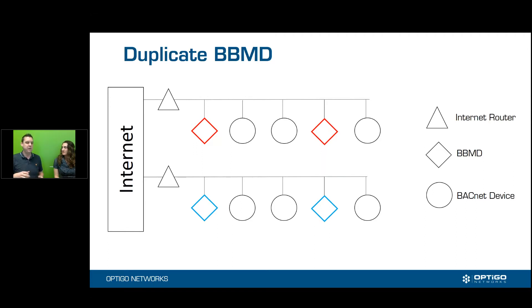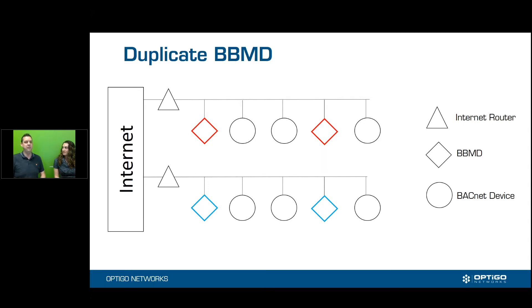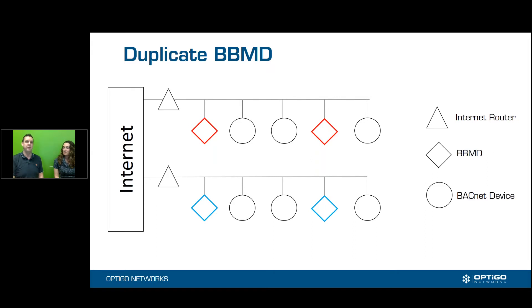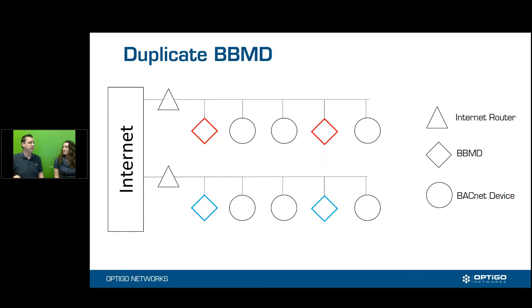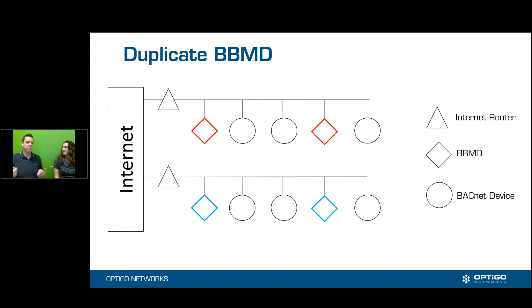Typically it's from a mixed vendor site. So vendor A, vendor B, vendor C. So if you think about vendor A, it comes along and says, I want to connect all my sites together. They enable BBMD functionality. It's all connected. Second part of the job is vendor B puts their controllers on the network and says, I want to connect all these networks to my front end. So now you have the first duplicate BBMD.